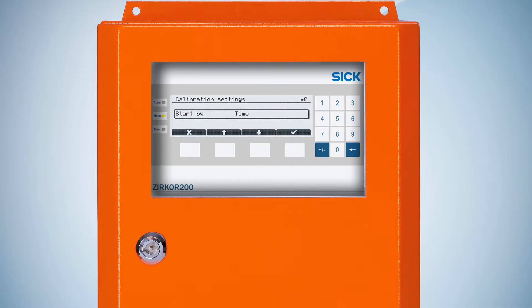If you choose time, your ZIRKOR200 will perform a calibration at specified time intervals automatically. With time and digital input, you still need to configure an interval. To start the calibration, the defined time interval needs to have elapsed and the operator has to start the calibration by digital input. In this case, we select time.